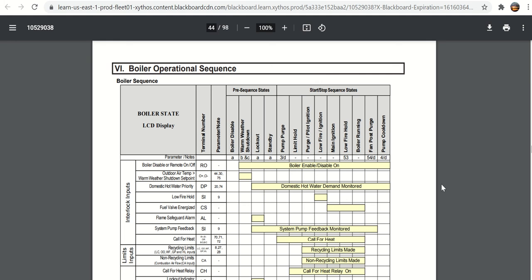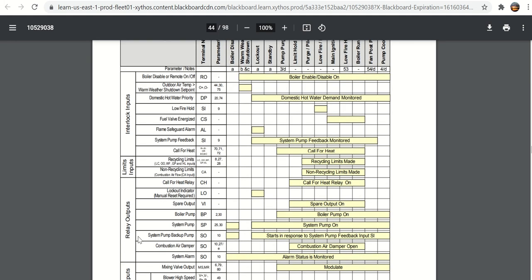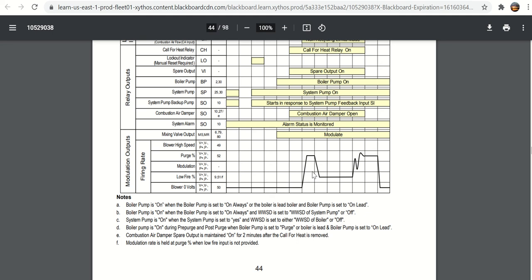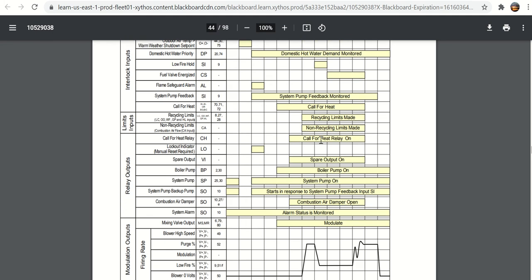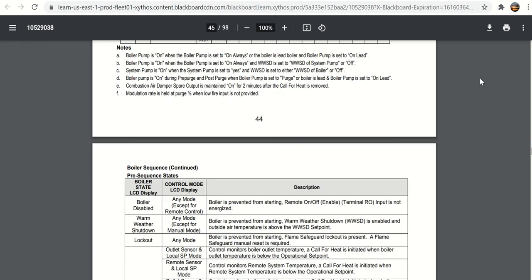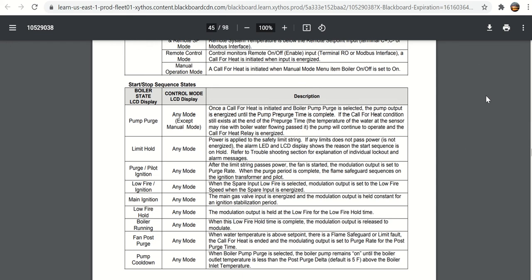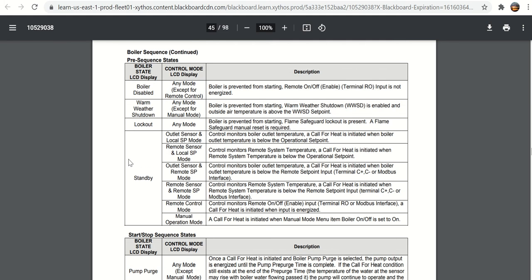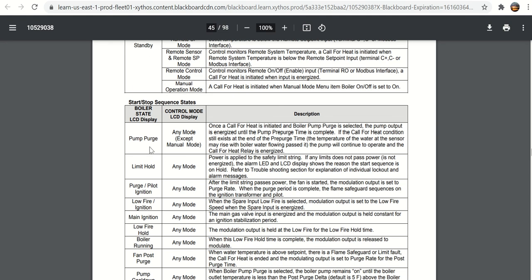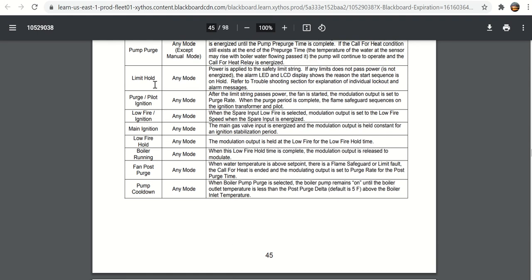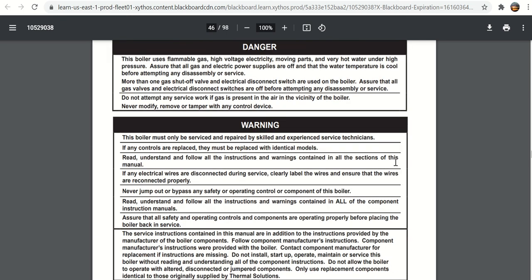But here's kind of a boiler sequence, interlocks, limits, relay outputs, and how things happen. You know, the blower voltage, blower high speed, blower low speed, kind of how things work in sequence. Even though they're using a traditional flame safeguard, there's a lot of things in there. Here's the LCD display. It will tell you if the boiler is disabled, whether it's warm weather shutdown, which means that the outdoor temperature is higher than a temperature you need to run the boiler. A lockout condition, whether the boiler's in standby. All this information to tell you whether the pilot's on, the low fire ignition, main ignition. All of this stuff will show up on the display.